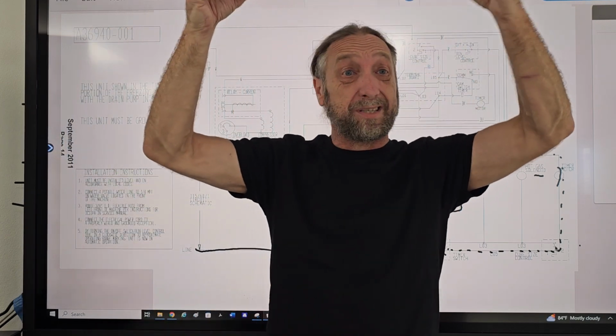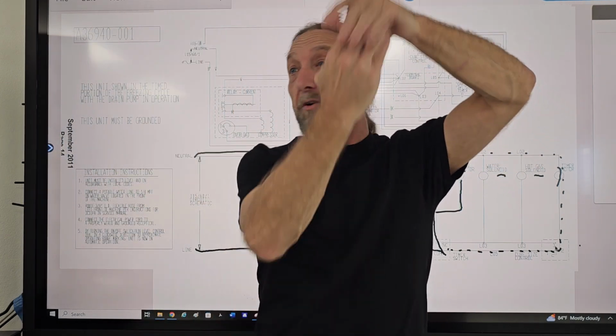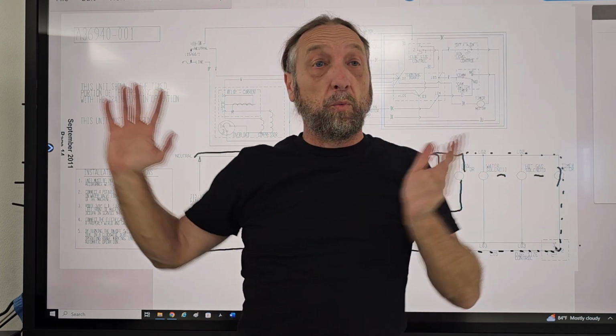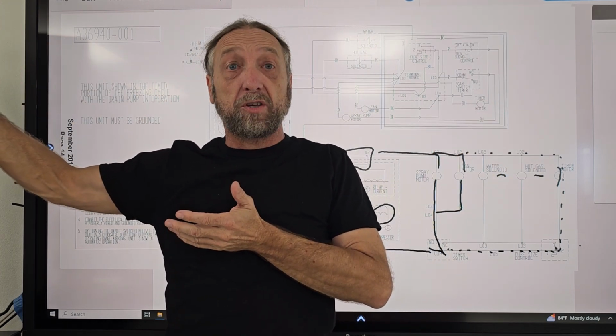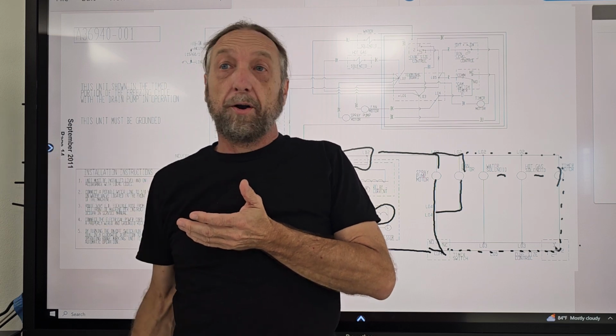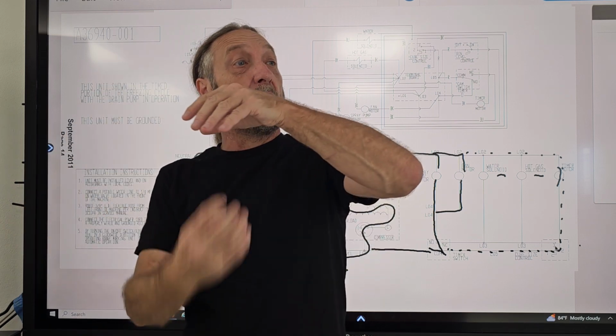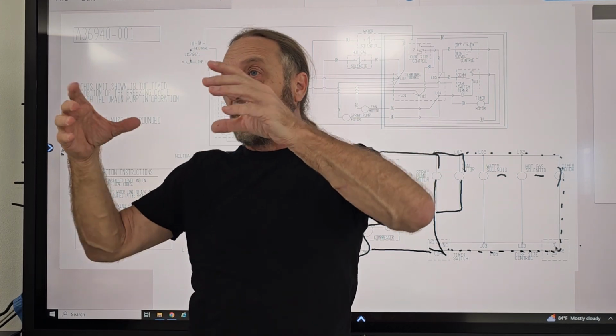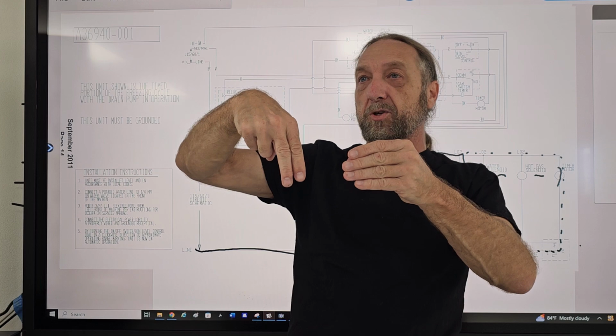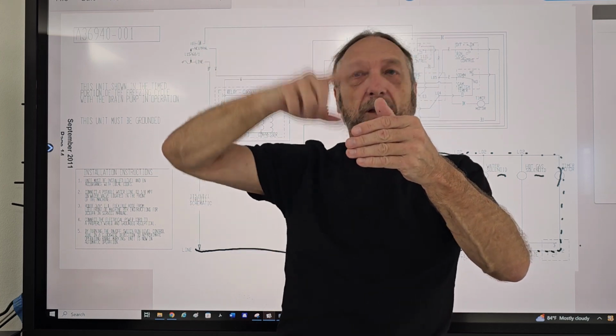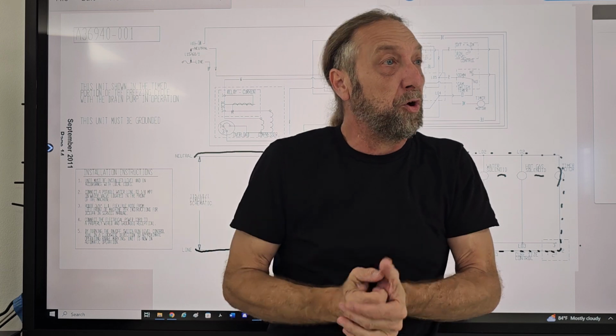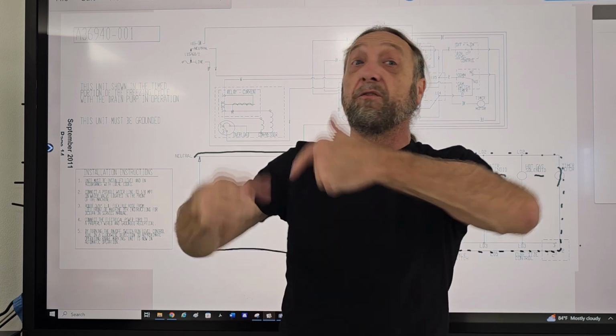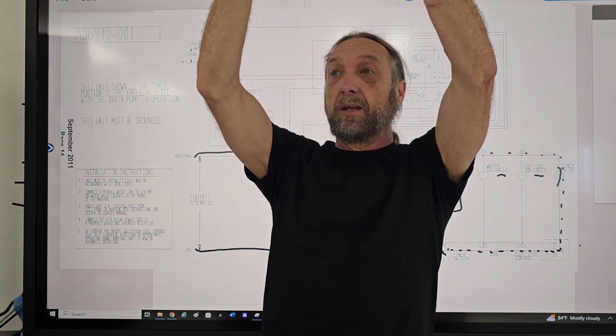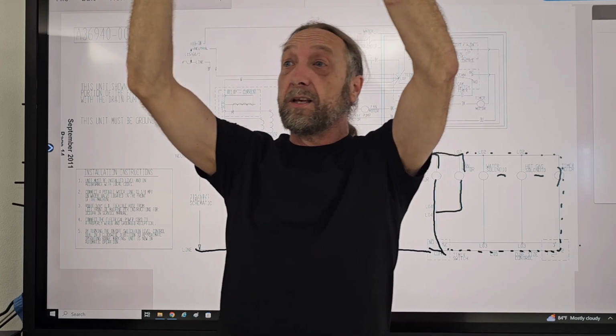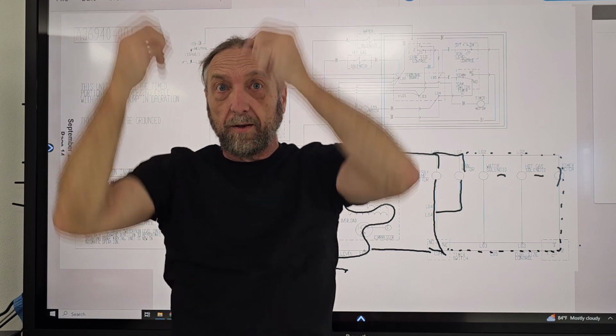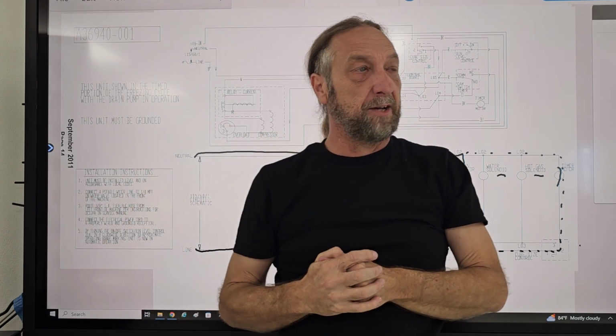It's just the evaporator itself is so cold, the water sticks to it. That's it. We're running at 15 degrees below zero in the evaporator, just like a refrigerator evaporator. And the water hitting it, every time it goes up, it's getting cold from that evaporator. So if you put your hand in the water at first, it'd be room temperature. But as it's circulating through, it's getting colder and colder. You stick your finger in there, that could be 30-degree water. Now it won't freeze if it's moving, but once it throws up onto the evaporator at 15 degrees below zero, that's another 40 degrees colder. And that's going to stick there, and that's how the ice is produced.